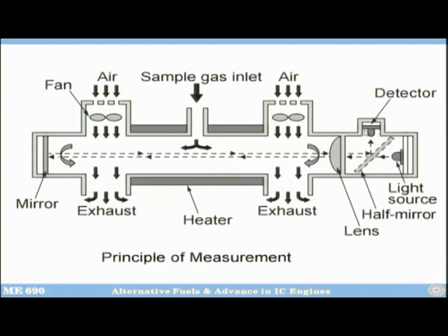So, now in this case, what will be the length of the tube, from here to here, or not? Actually, the length will be from here to here and here to here, because now the light is passing twice in the exhaust path. So, actually the length will be twice, and that is why I said that you are trying to make the instrument smaller and smaller, otherwise you have to have very long tubes. So, by doing this kind of improvisation, you can make the sampling unit very, very small.